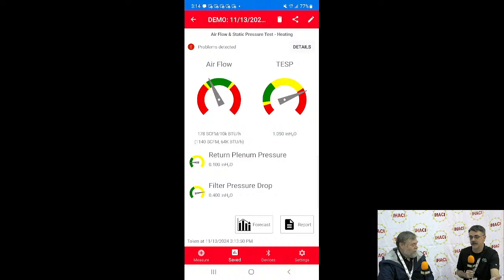It's really easy to show the difference between those two, and it's a great visual to show the homeowner. Say, look, here's what this is costing. Do you know how I used to do it in the old days? I had a Magnehelic. I'd say, you watch that Magnehelic, and I'm going to take that filter out and put a clean one in. It's pegged, take that one out, now it's back at a half inch. And suddenly, oh wow. That was the old days.